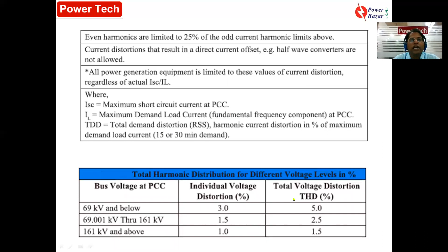Why do I have to nullify harmonics? Because harmonics are not a good element. They are a nuisance. They create disturbance, flickering and tripping. They cause heat losses, for which filters are required. Now, who is responsible? The customer is responsible for maintaining current distortion, but the utility is responsible for limiting voltage distortion. That means my utility should give me a sinusoidal waveform, but because of my load, I may get a distorted current. So once I rectify my current distortion, I will not be polluting the supply side or utility side.